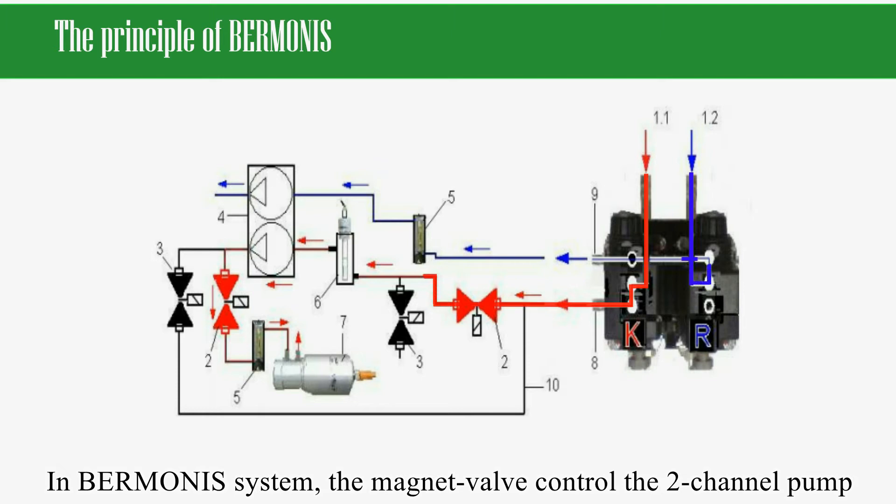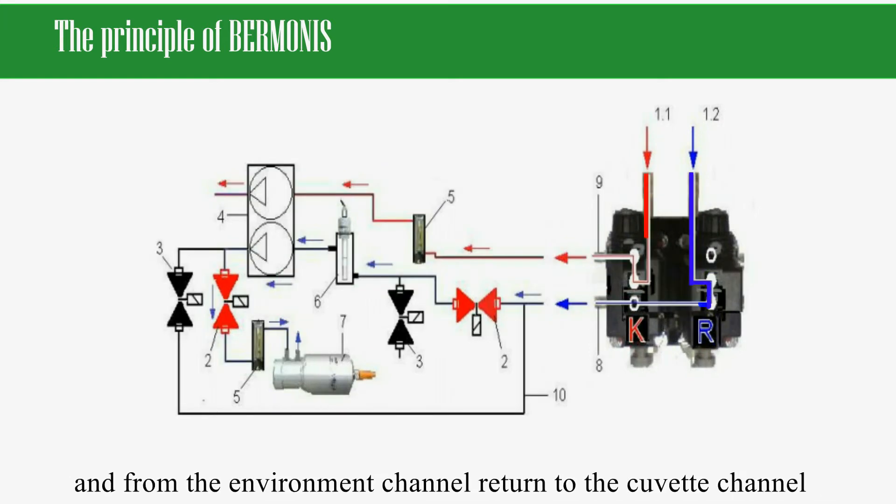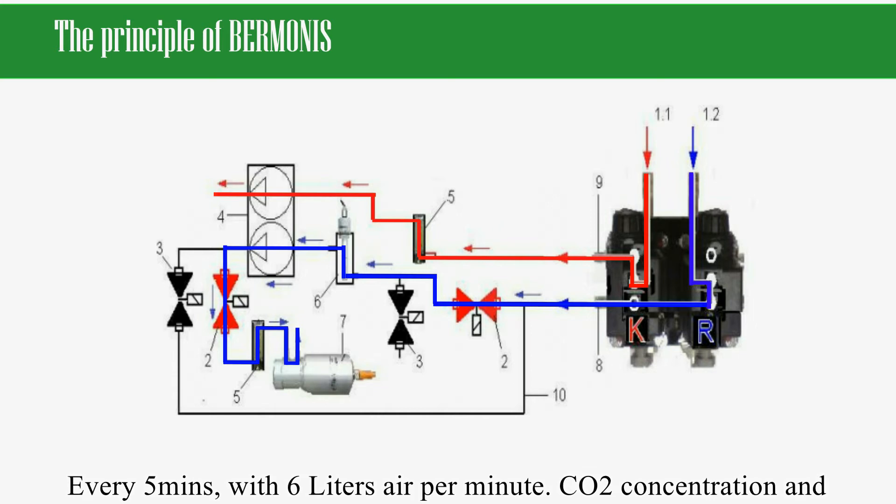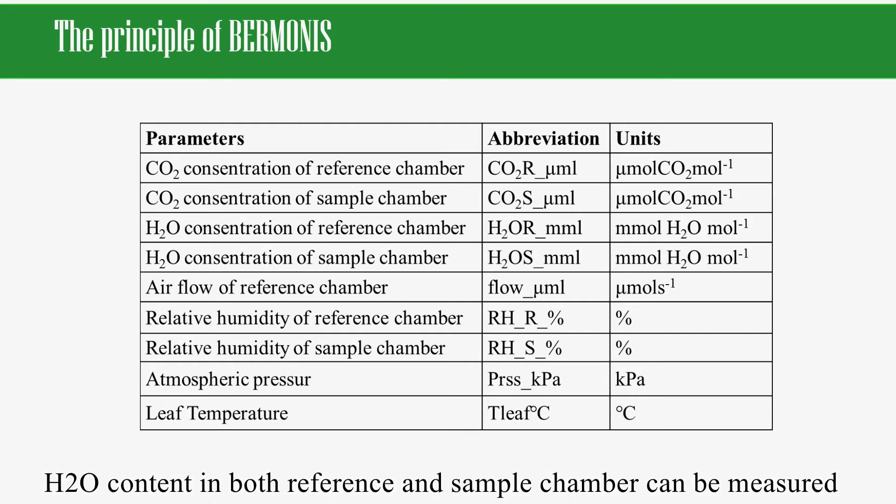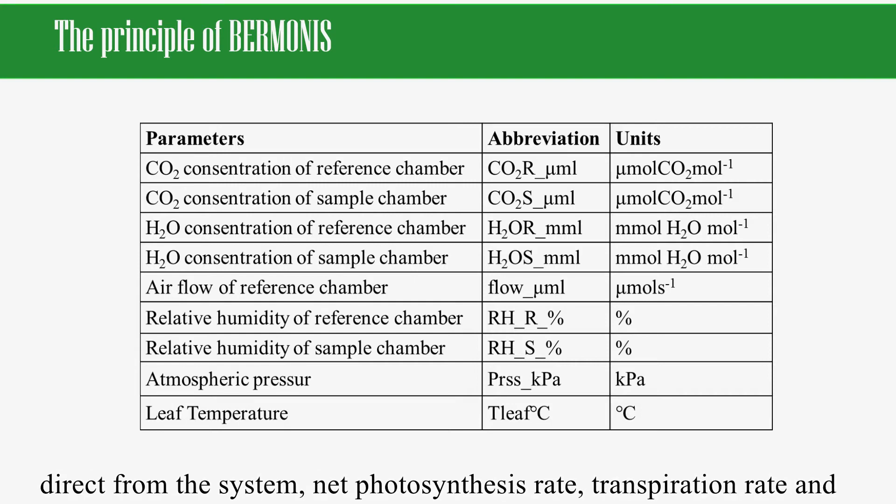In the BERMONIS system, the magnet valve controls the two-channel pump to change the air from the cuvette channel to the environment channel, and from the environment channel return to the cuvette channel every five minutes with six liters of air per minute. CO2 concentration and water content in the gas molecules can be measured directly from the system.